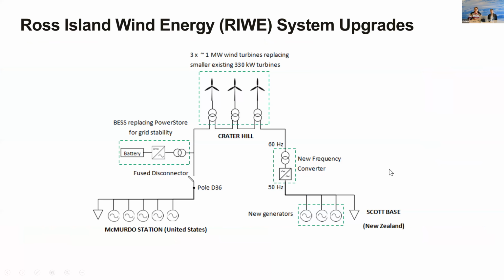As part of our upgrades, we pretty much have to upgrade the entire grid. Starting at the top of this single line diagram, you can see 3 wind turbines - the 3 existing Enercon E33 turbines, each rated to 330 kilowatts. We're replacing those with 3 1-megawatt wind turbines that largely go in the same area, since there aren't too many places you can put wind turbines on Ross Island. They're slightly more spread out because they're a bit bigger.